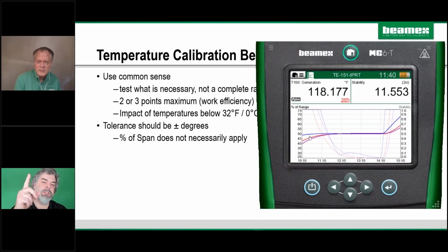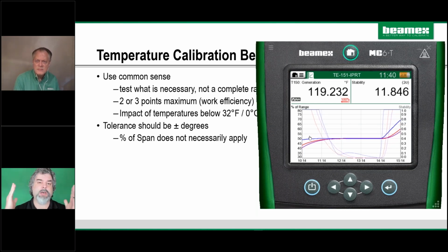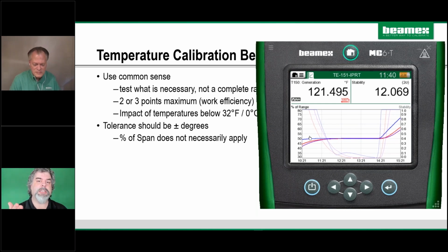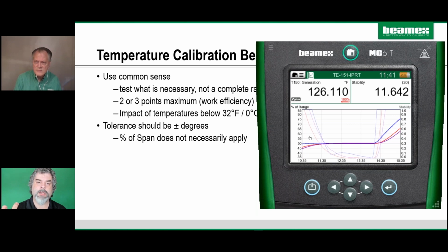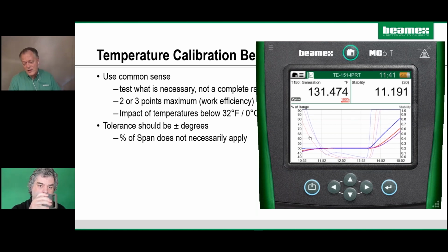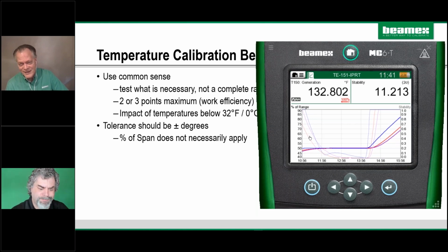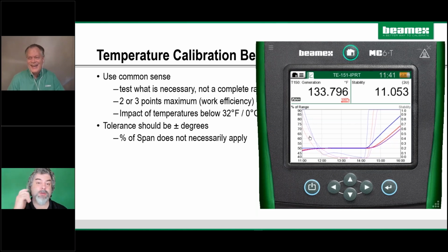Okay. One comment I wanted to make on making an adjustment on a probe, and this is not an adjustment, but if you have an expensive temperature probe, a nice IPRT that's been shocked or dropped, the crystalline structure could actually be offset, and it could affect your measurement or your reading, and it is possible to resolve that by annealing. And annealing means put it in a heat source that is up to the maximum level, super hot, of that probe, and it'll realign the crystalline structure. That's pretty extreme. Yeah. So if you need to do that, you call Roy. Don't call Ned. Don't call me, I'll be on the phone just to. Yeah.